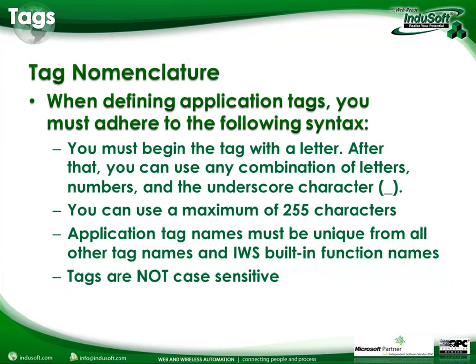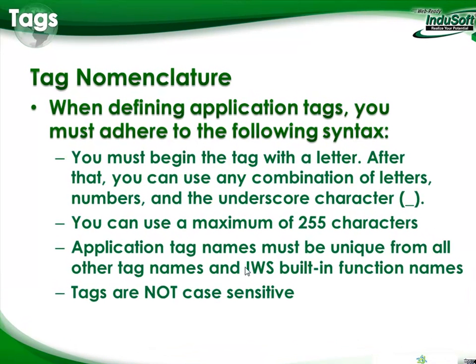Application tags must be unique from all other tag names and built-in InduSoft functions. For example, you cannot name a tag the same as a system tag — such as date, month, or seconds clock — and you cannot name tag names the same as other built-in scripting functions. Also critical: tags are not case sensitive. Even if you don't use the same case, it's irrelevant — they are all the same.